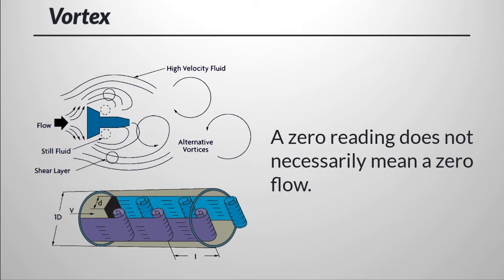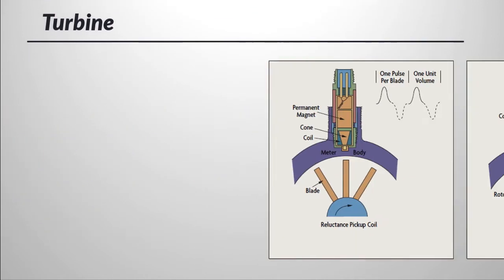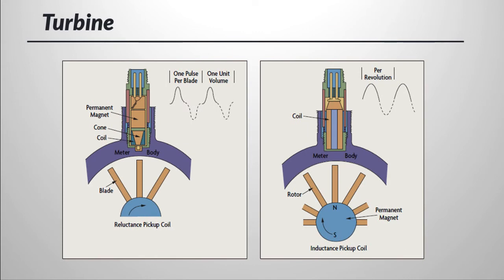A turbine flow meter consists of a multi-bladed rotor mounted at right angles to the flow and suspended in the fluid stream on a free-running bearing. The diameter of the rotor is very slightly less than the inside diameter of the metering chamber, and its speed of rotation is proportional to the volumetric flow rate. Turbine rotation is detected by solid-state devices or mechanical sensors.